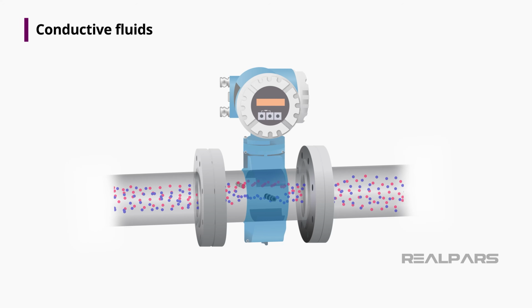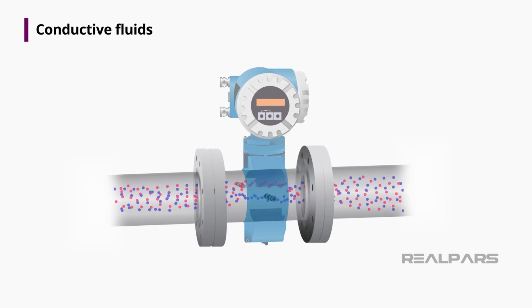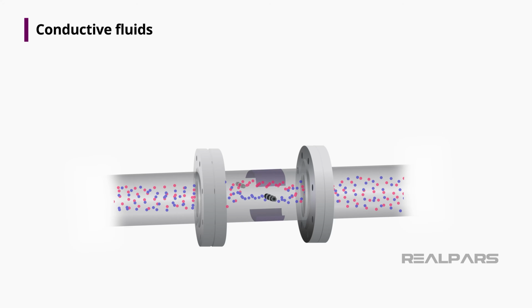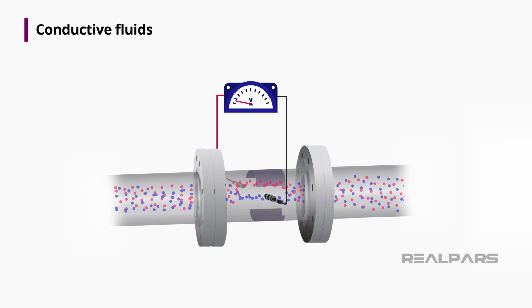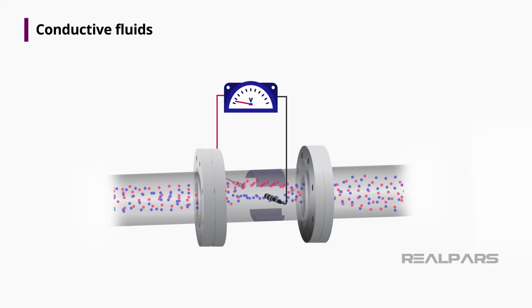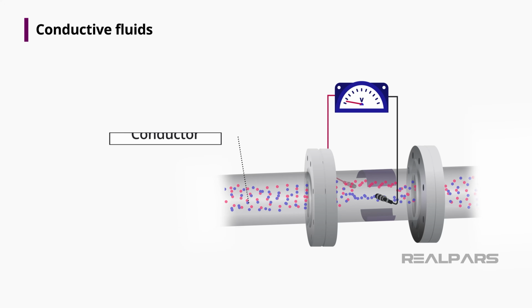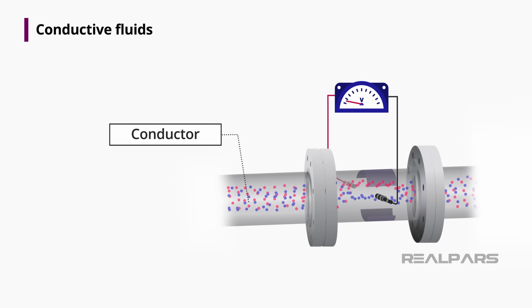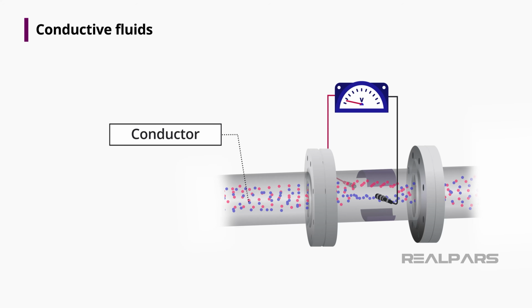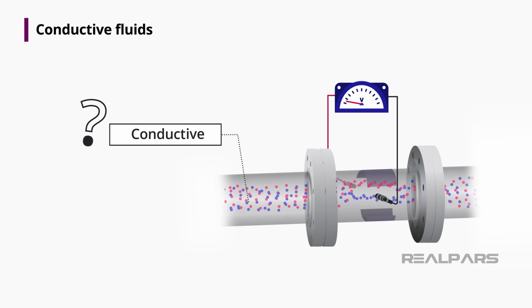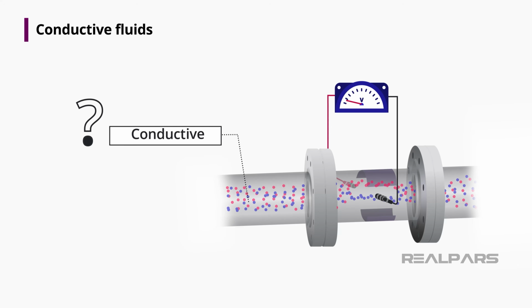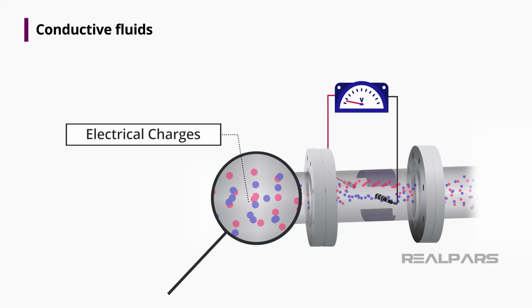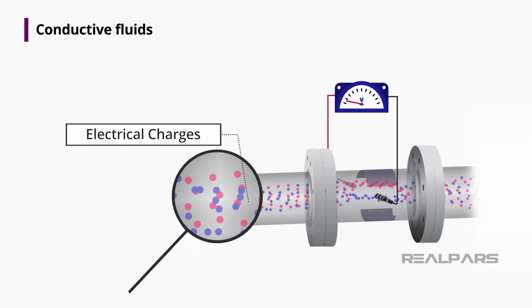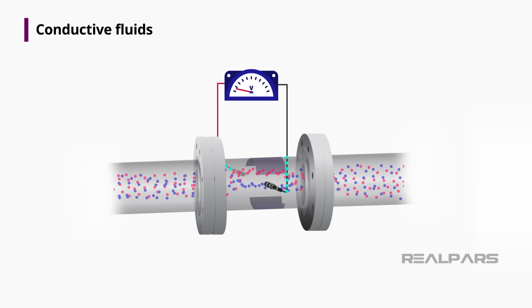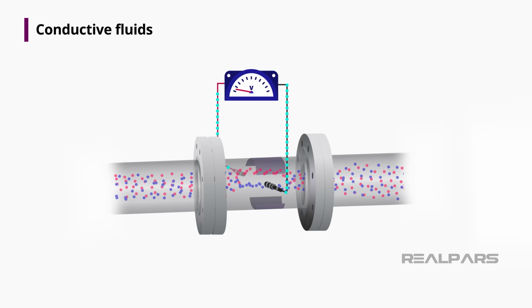But there is one key parameter that cannot be overlooked that I mentioned previously. We must have a moving conductor to generate the required electrical signal. I said the flowing fluid was the conductor, so the fluid must be conductive to work with a magnetic flow meter. What does it mean for a fluid to be conductive? It means that the fluid must be able to conduct an electrical charge, thereby establishing a voltage that can be sensed by the mag meter's electrodes.